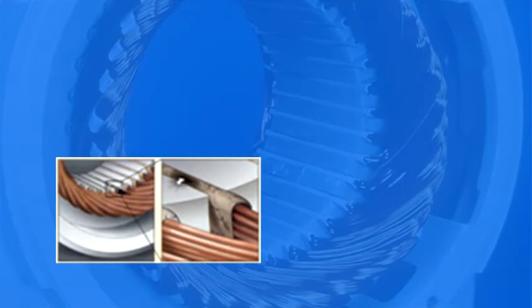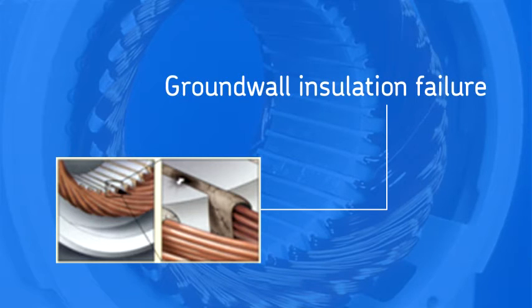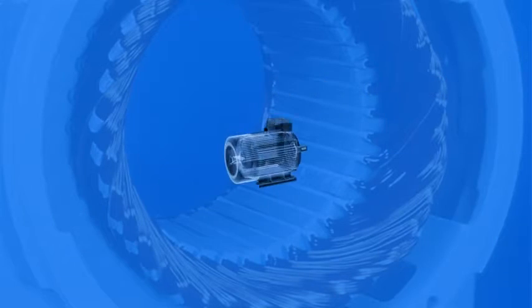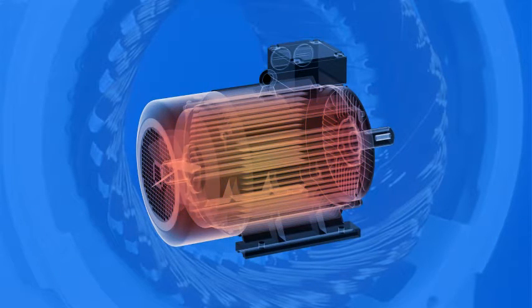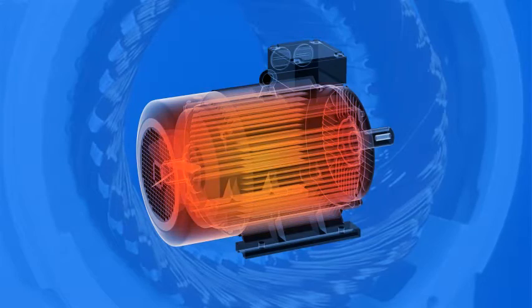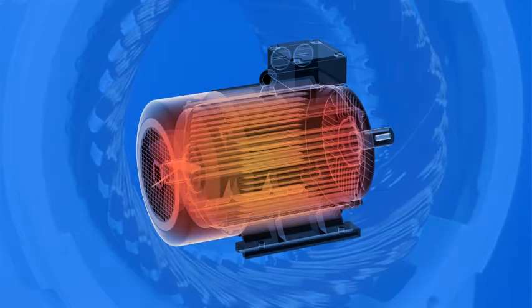When the insulation fails and there is a path to the core, it is called a ground wall insulation failure, since the stator core is at electrical ground. Oftentimes, when a motor overheats or has a turn-to-turn failure, the excessive heat will cause a ground wall insulation failure also.